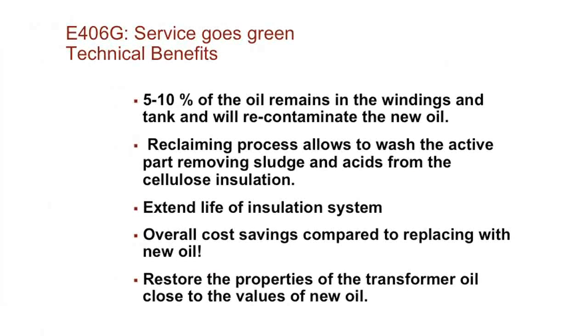The technical benefits are primarily compared to oil exchange, where we drain and replace with brand new oil, versus the reclamation process. The negative side of just draining and replacing is that you leave 5 to 10% of the oil within the insulation system, the windings, and the bottom of the tank that you cannot remove. Over time, I have a chart that shows a leaching effect of that high acidity oil back into the new transformer oil, and you see an increase in acidity in the new oil in the first 6 to 12 months.